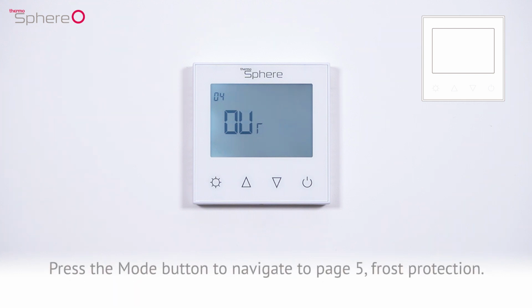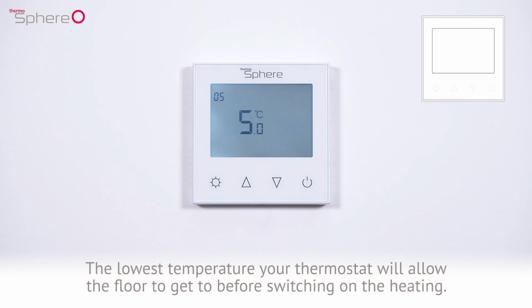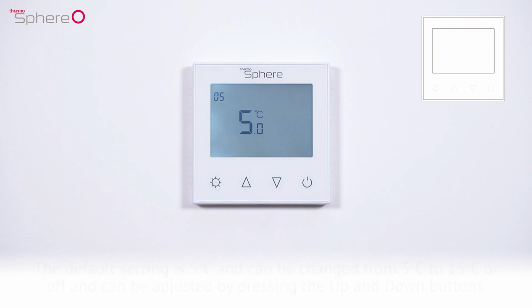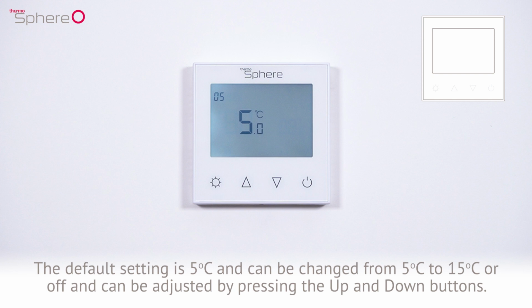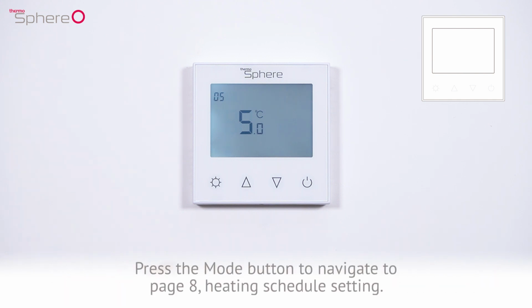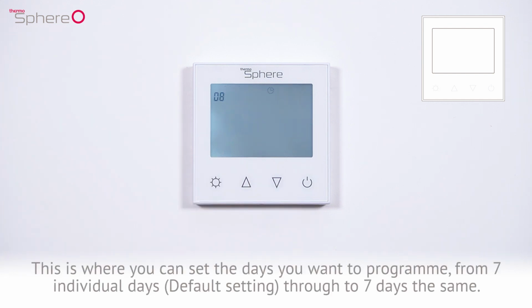Press the mode button to navigate to page 5, frost protection. This is the lowest temperature your thermostat will allow the floor to get to before switching on the heating. The default setting is 5 degrees Celsius and can be changed from 5 degrees Celsius to 15 degrees Celsius, or off, and can be adjusted by pressing the up and down buttons. Press the mode button to navigate to page 8, heating schedule setting. This is where you can set the days you want to program, from 7 individual days, which is the default setting, all the way through to 7 days the same.